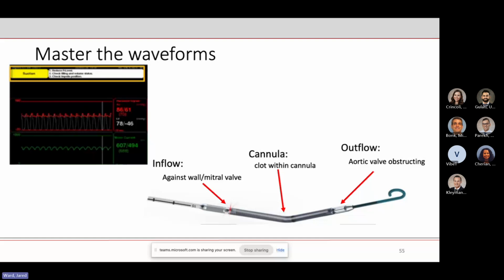The bleeding issue, you just got to make sure it's up at 30 degrees and is sutured forward, and just make sure the peel-away sheath isn't there. The issue I've seen is usually with patient positioning, like when they get transferred from bed to bed, they'll change the angle of their leg, and then you have to adjust the angle yourself. It's generally because the angle's too shallow, or it's not sutured forward tight enough. You can just throw extra sutures in to make sure it gets pulled tighter against the skin, and then make sure that the angle is more appropriate, like that 30 to 45 degrees.